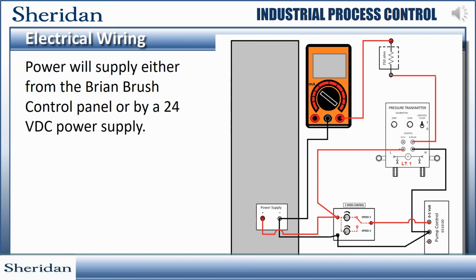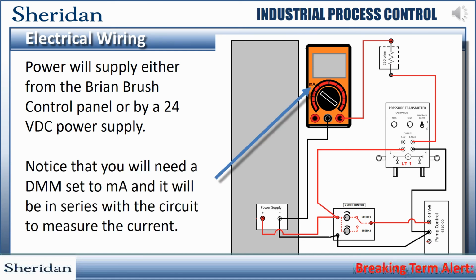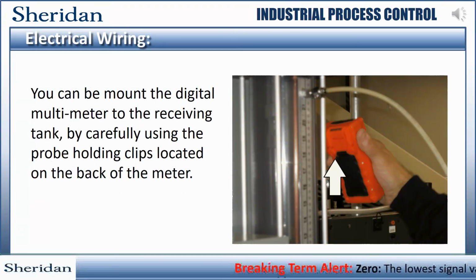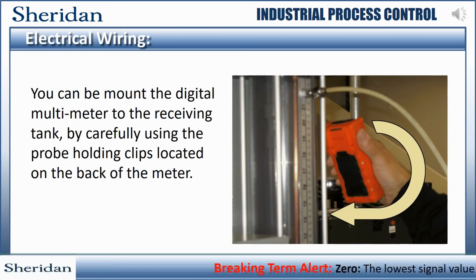The power for the lab will be provided by the 24 volt taps on the Brian brush control panel. If the station you are working on does not have the control panel, then you will use the 24 volt power supply. Notice that you will need a digital multimeter set to milliamps. This means you must wire the meter in series with the monitored signal to determine the current. You will be required to monitor the digital multimeter during calibration.